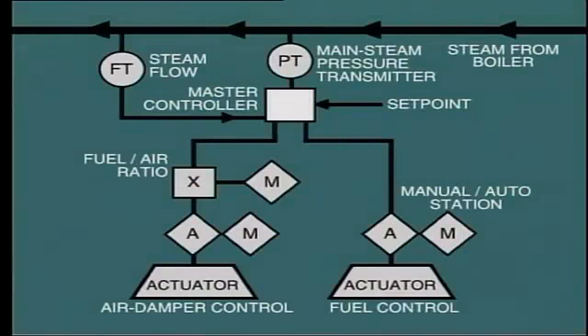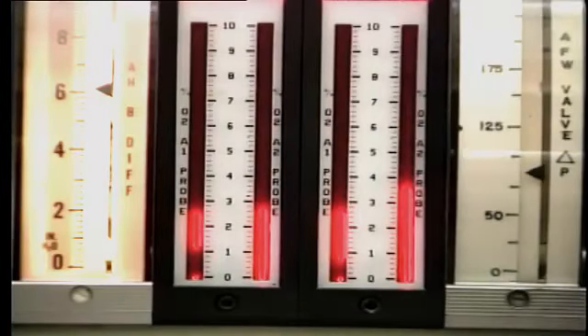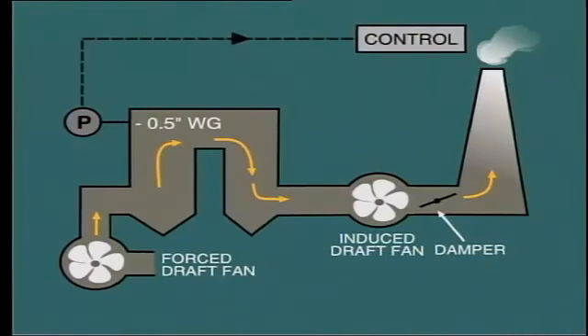A further improvement may be obtained by connecting the oxygen analyzer signal to automatically adjust the fuel-air ratio. This acts as a trimming device to precisely control the combustion air and bring the excess oxygen in the flue gas to the desired set point. Auto control of induced draft, where fitted, is not usually considered part of the combustion control system as it is operated by a separate dedicated control loop. The controlling parameter is measurement of furnace pressure — that is, negative pressure — with the controller set to maintain about minus 0.5 inches water gauge in the furnace, achieved by adjustment of the ID fan dampers.